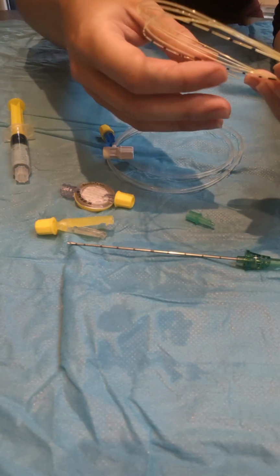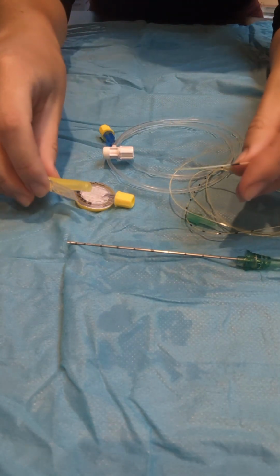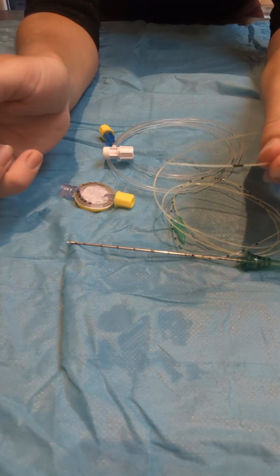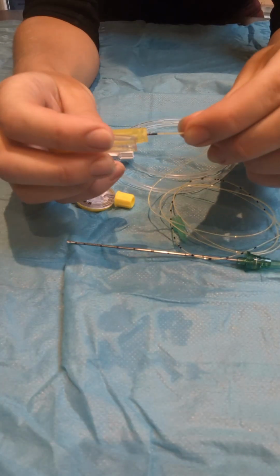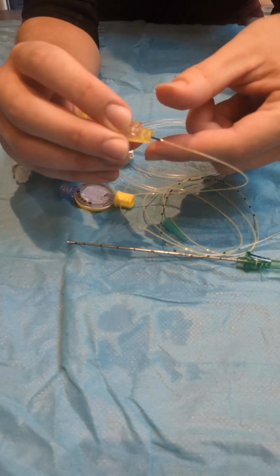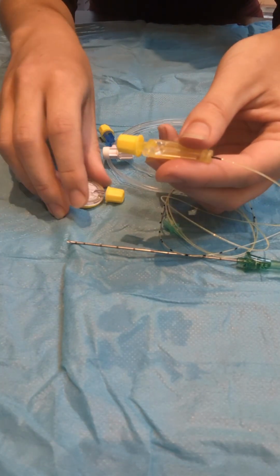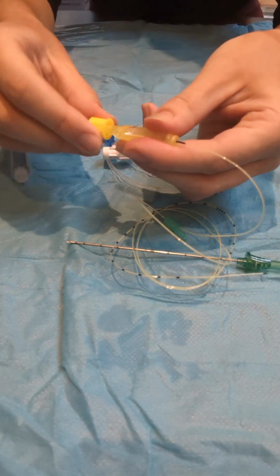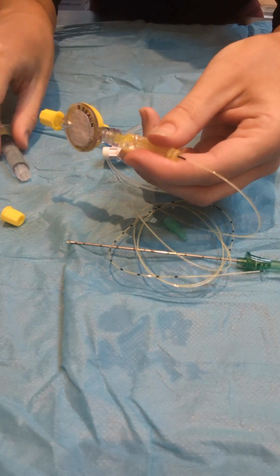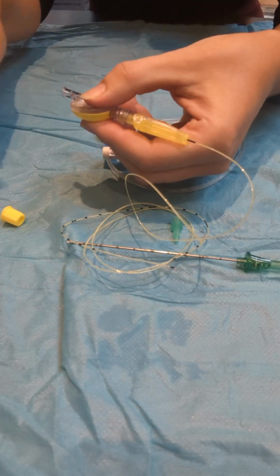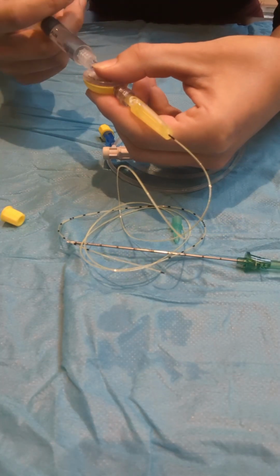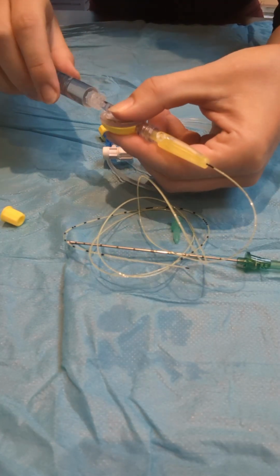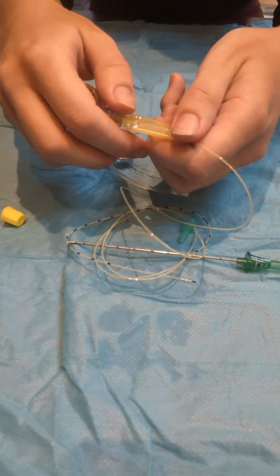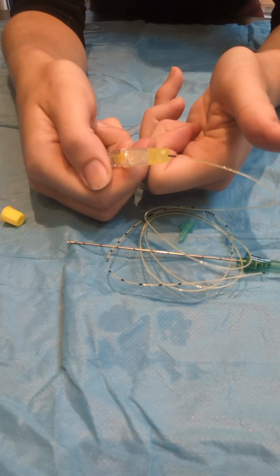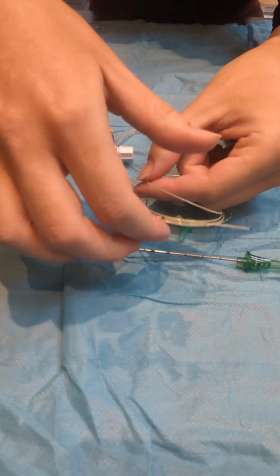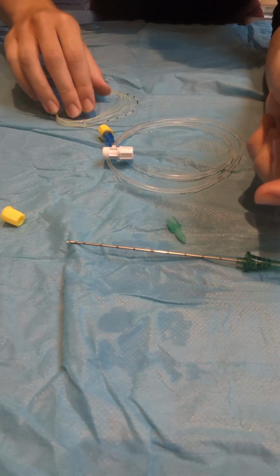So first of all, you need to prime your set. So you take the end of your catheter, insert the clamp until the black line and click it in position. I then usually also prime the filter at the same time. You take your syringe and flush it until you see the fluid emerge. You then disconnect your syringe and, using a levering technique, release the clamp to allow you to remove the primed set.